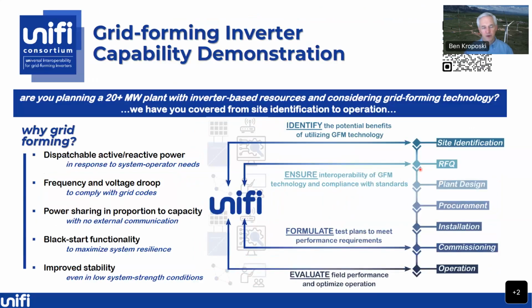And then we want to go bigger than that. We are looking at 20 megawatt plus demonstrations of grid forming technologies. And this is where we're going to have inverter-based resources that are going up to this really utility scale. The one reason I'll point this out here is that if you are listening to this webinar and would have some place where you are thinking about putting grid forming inverter technologies at over 20 megawatts, we'd be very interested in following up with you.